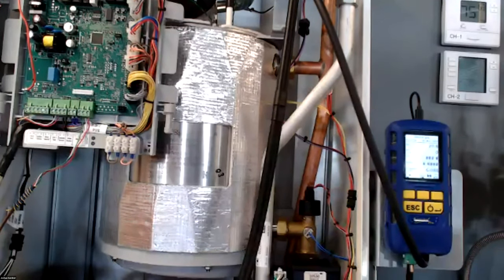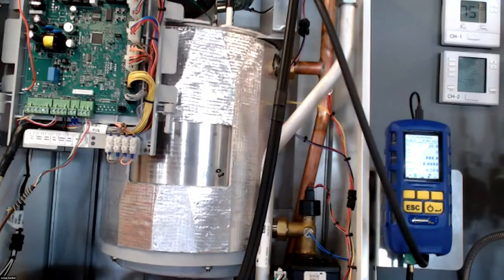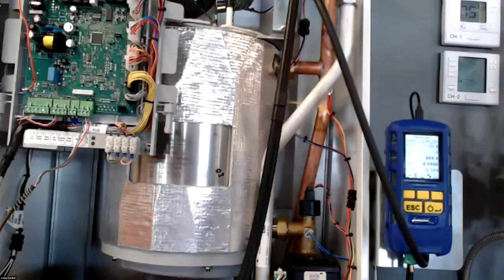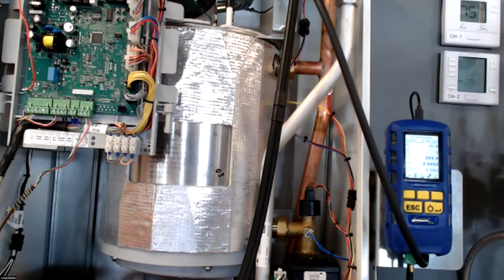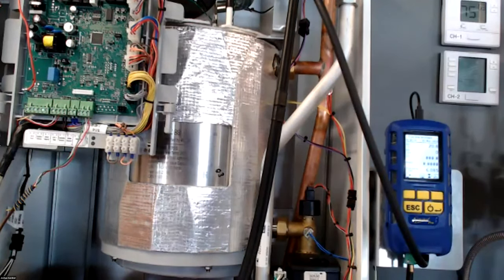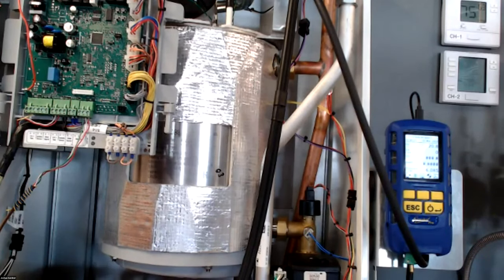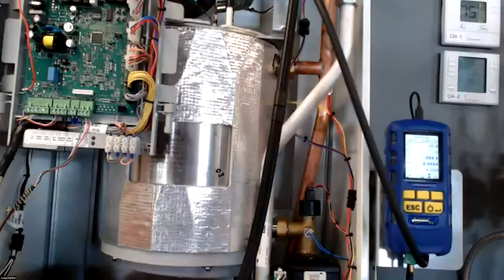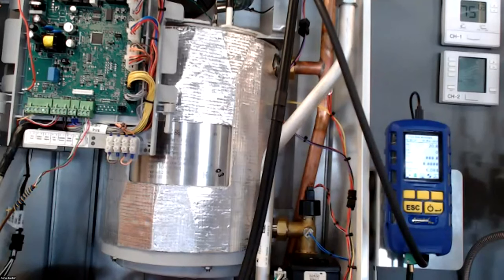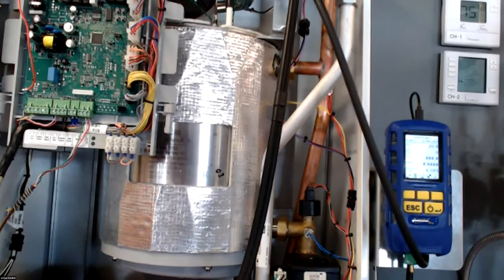I wouldn't have put 100% on the accuracy of this gas valve. We've made this thing fail on purpose. This thing's probably been adjusted 2,000, 3,000 times, and the offset, so yeah, if it was off a little bit, okay, I wouldn't be concerned with this one. In the field, it definitely should be on, but these boilers are training boilers. We put these through the paces, let's say. They run pretty rough. We run these things down to 1% O2, up to 10%, to try to get them to kick out. They've been through a lot.